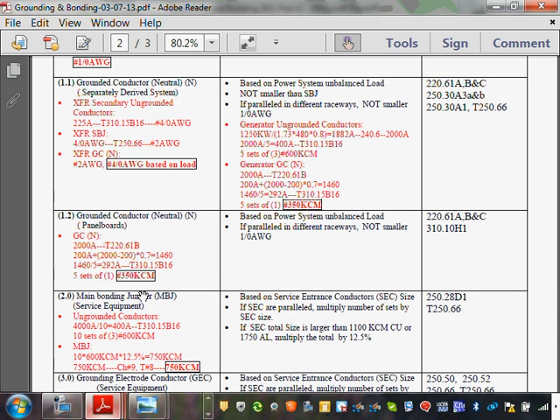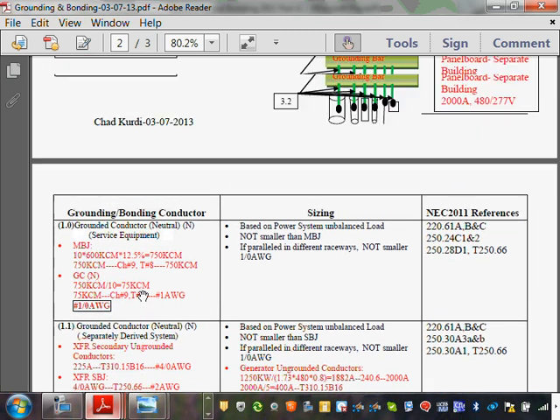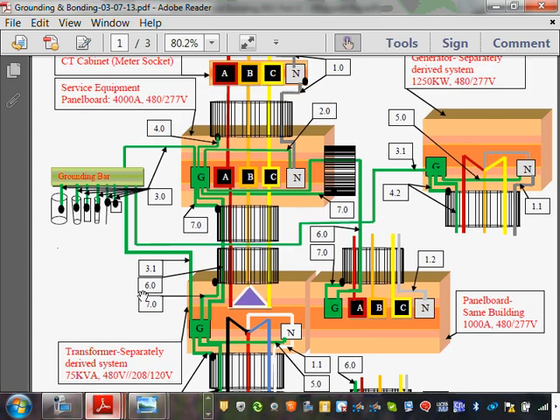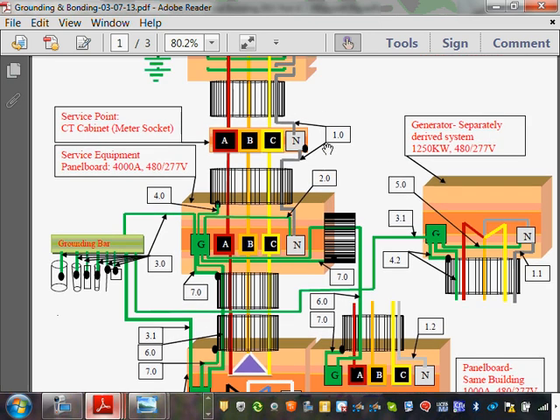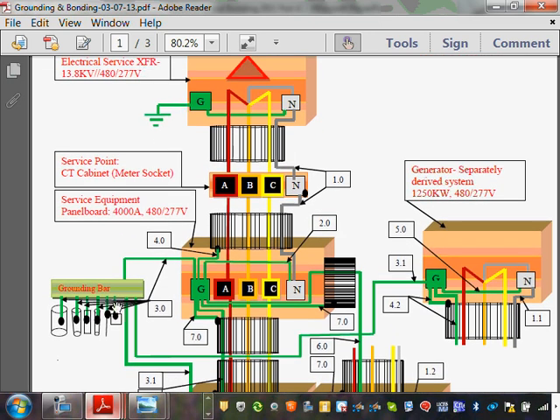Okay, so let's go. You are familiar with the main bonding jumper. Now we bonded the grounding electrode of the utility to the grounding electrode that we own, operate, and created. Now we have another thing called the bonding jumper.